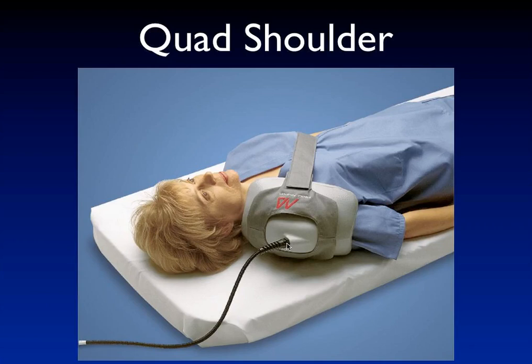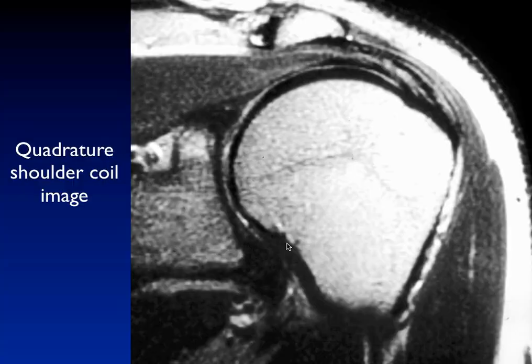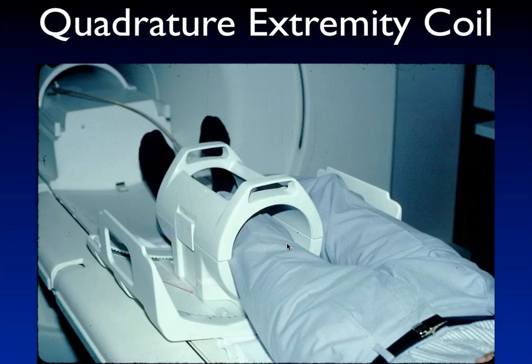Here is a quadrature shoulder coil. By definition, a quadrature coil is more complex than a single wire — it requires coils in two directions out of phase with each other by 90 degrees to receive only properly polarized photons. Quadrature technology also substantially improves signal uniformity compared to linear technology. The first coils were linear; in the late 1980s we substantially improved signal-to-noise by switching to quadrature coils.